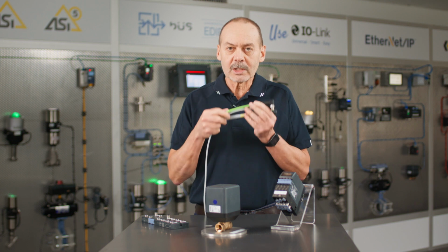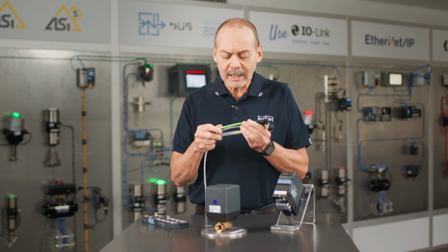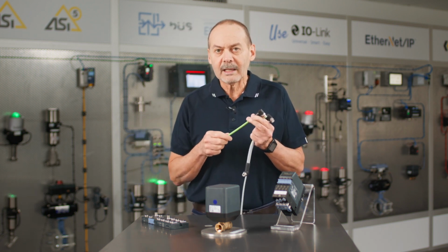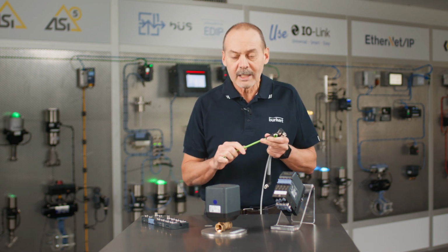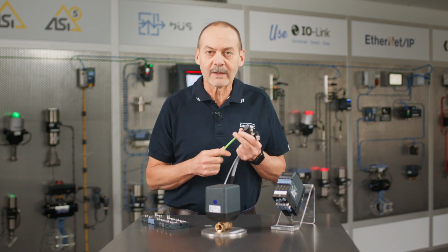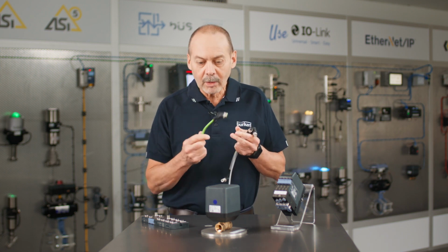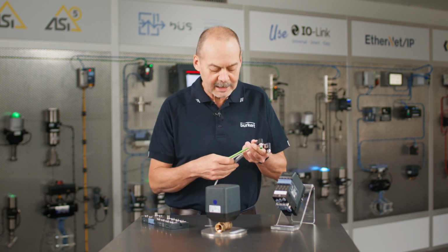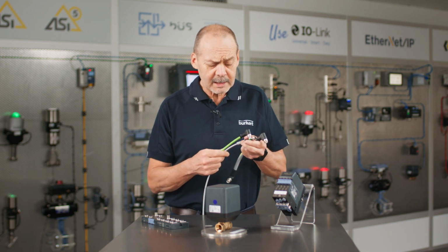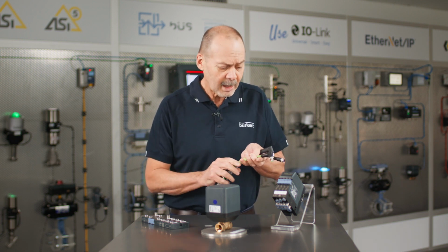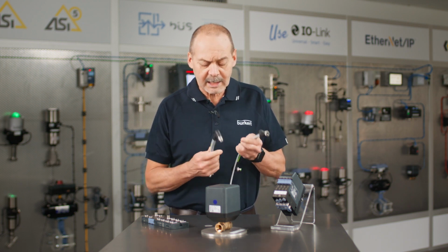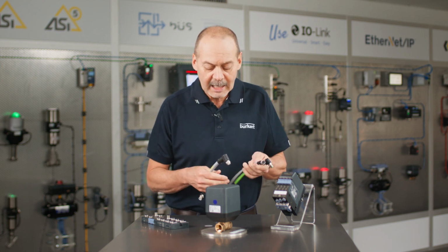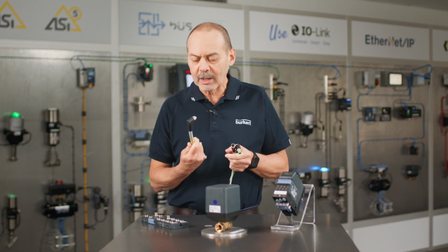What's also important with these is choosing the cable. So you have to make sure that the cable is fit for purpose. In other words, if it's on robotics and you use a stiff cable, then you'll find your cable's not going to last very long. So you're going to have to choose a cable that's actually perfect for that high flex application. More importantly, things like UV stabilization because of mounting out in direct weather and sunlight, etc., as well as things like the size and shape of it as well. So always get UV stabilized, always meet the site standards as far as the IEC or site standard colorings, etc., for things like Ethernet. And yeah, special word on the L-coded power.